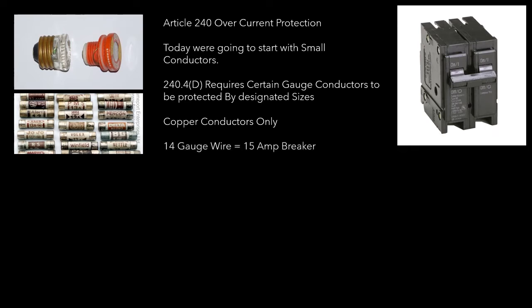When we're dealing with 14 gauge wire — regardless if it's Romex, THHN, THW, it doesn't matter — unless we're using some of the exceptions we're gonna talk about in a little bit, you're gonna be required to have that on no more than a 15 amp breaker. 14 gauge wire, 15 amp breaker, unless we're using some of those exceptions.